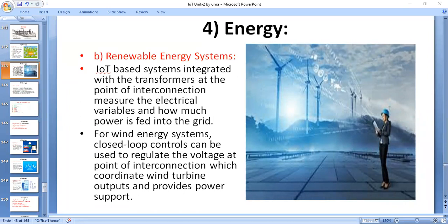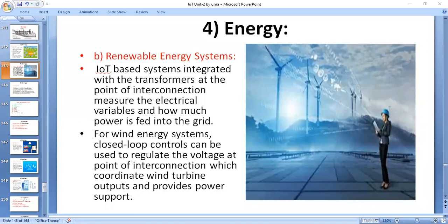When distributed renewable energy sources are integrated into the grid, they create bi-directional power flow for which the grid was not originally designed. The IoT-based system integrated at the point of interconnection measures electrical variables and how much power is fed into the grid. To ensure grid stability, one solution is to cut off power production. For wind energy systems, closed-loop control can be used to regulate voltage at the point of interconnection, coordinating with wind turbine outputs to provide reactive power support.